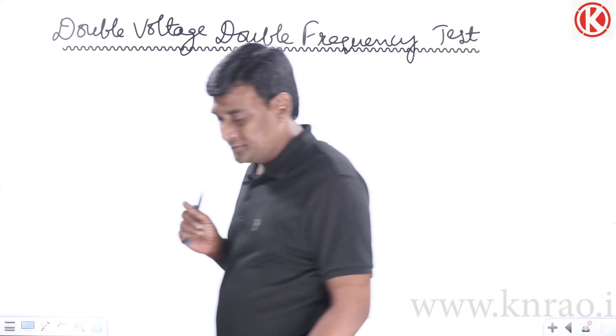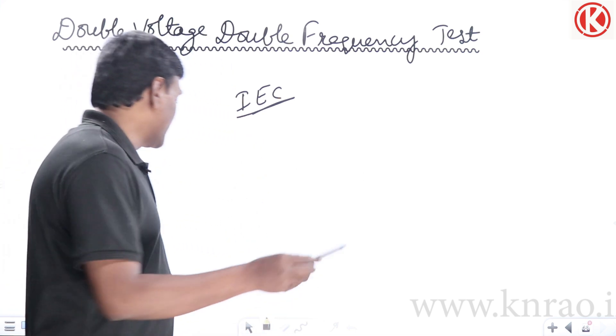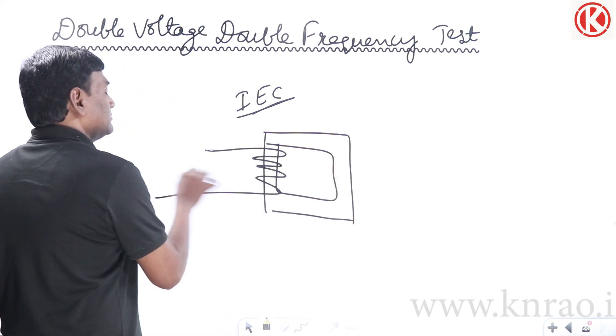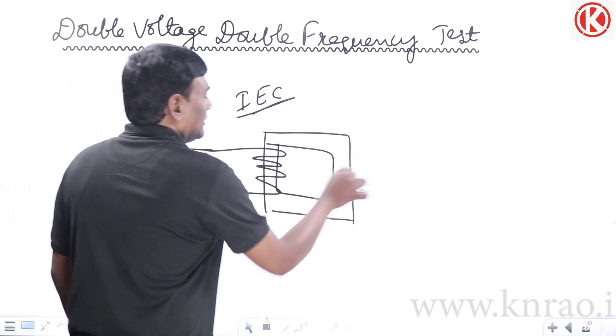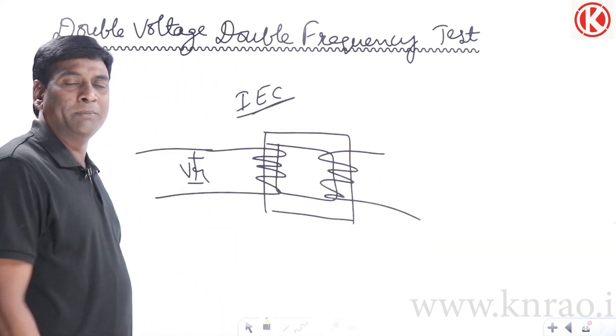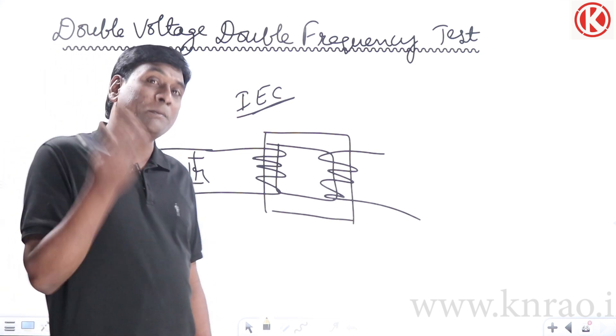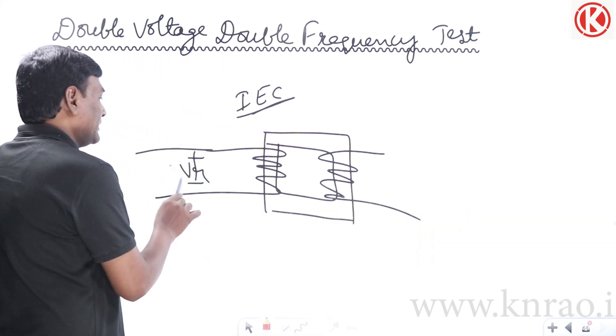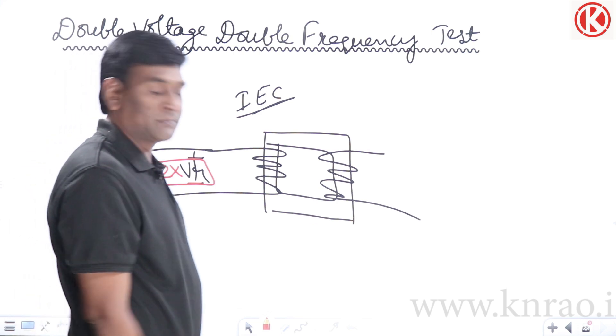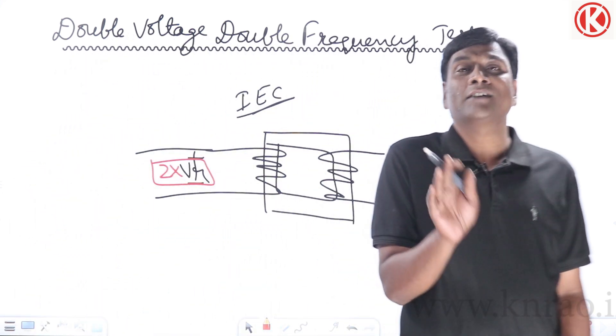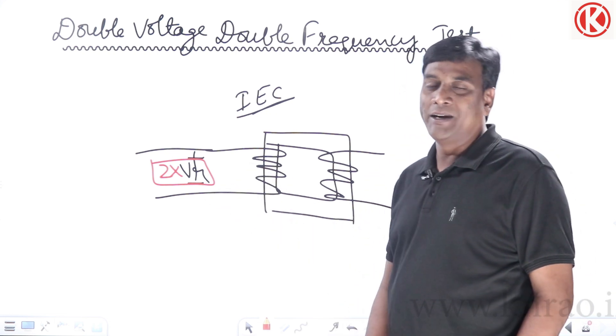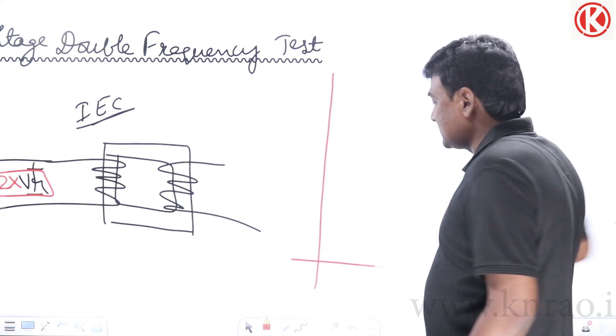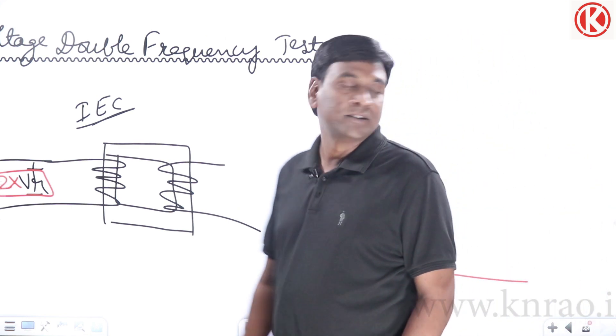Now consider our transformer: the supply voltage is the rated voltage V-rated. There will be no load on the secondary side because this test is only to test the insulation. So on the primary we are going to apply double the rated voltage — two times the rated voltage. But if we maintain the same frequency when doubling the voltage, what will happen?